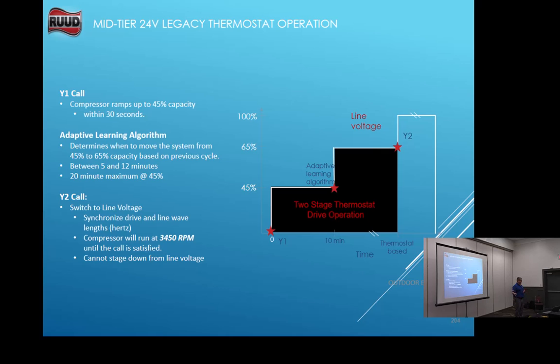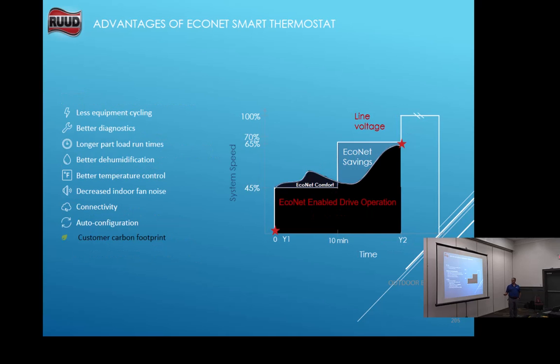But it works, and it's still more energy efficient than the 14 SEER. Okay? Gives us more temperature control. This is the difference between the two. This is where your EcoNet savings is, and this is where you lose some savings here between the fixed speed and the variable. You have more comfort control here than you do with the fixed speed. You don't have as much of a temperature swing. Okay?